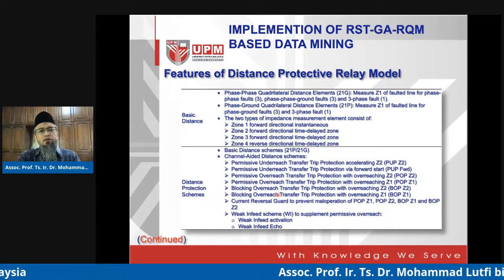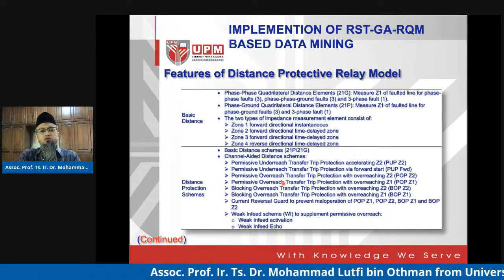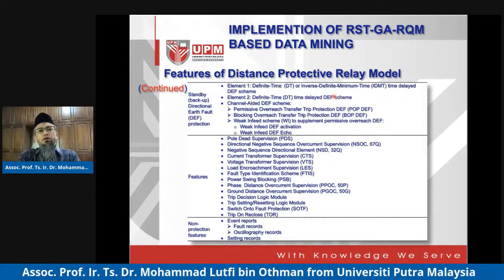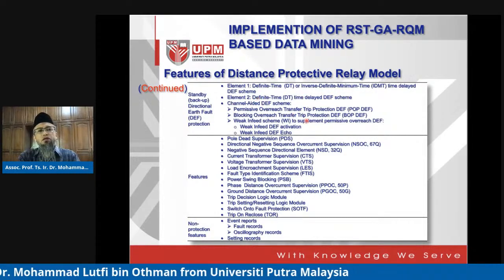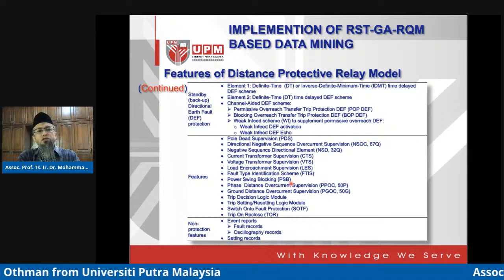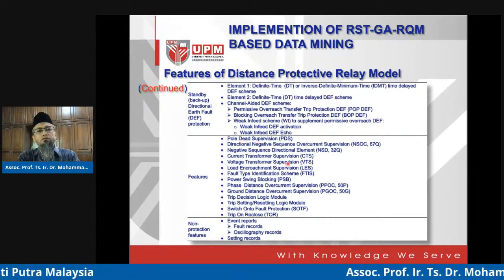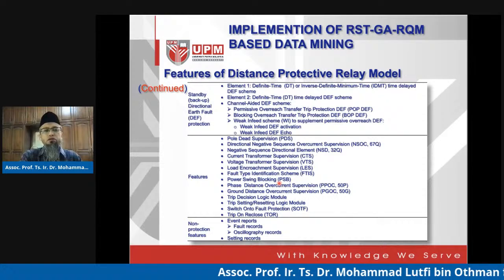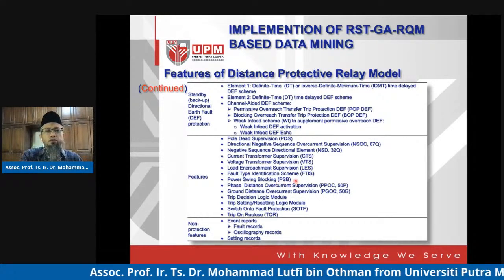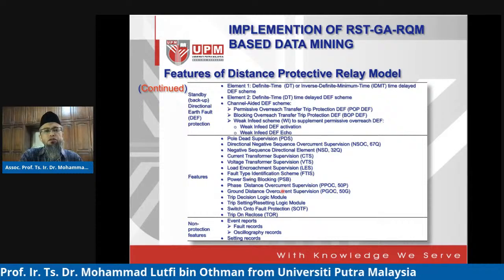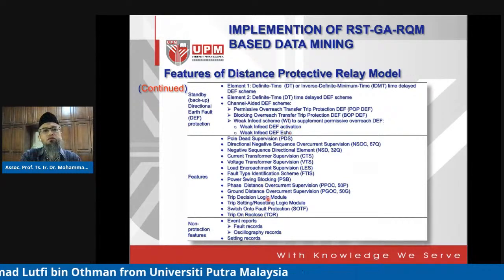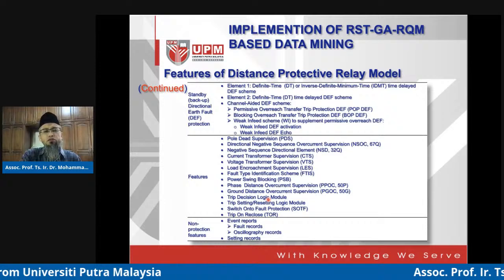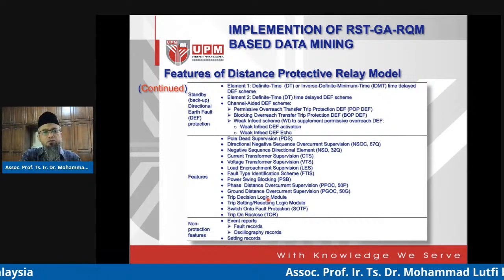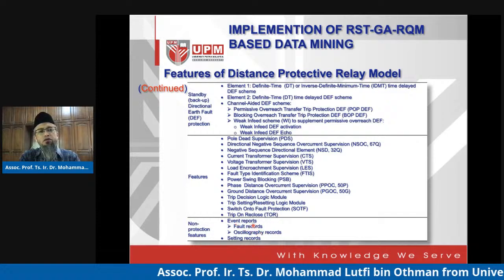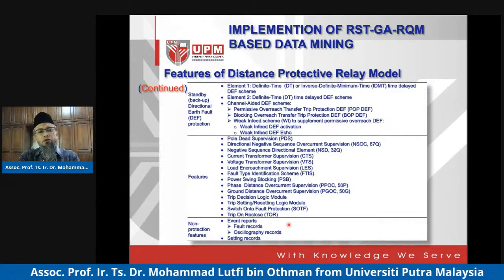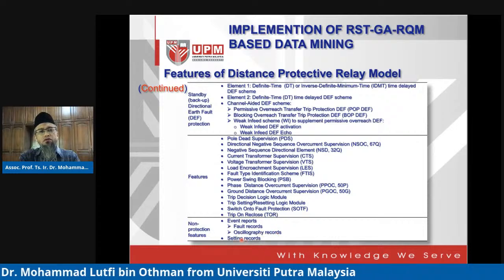The basic distance relay, other relays that underreach, overreach, supervision units, and then you have all other overcurrent relays, directional, non-directional, and other supervision units like the Pole Dead Supervision units. You have the power swing blocking unit I talked about, and we managed to file a copyright, and some other supervision like reclosure supervision as well. So these are basically what you may find in the manual that we have managed to model as much as possible. And of course, what is very much of our interest is the event record facility found in the relay: the fault recorder, the oscillography, voltage current records, and of course the setting records.